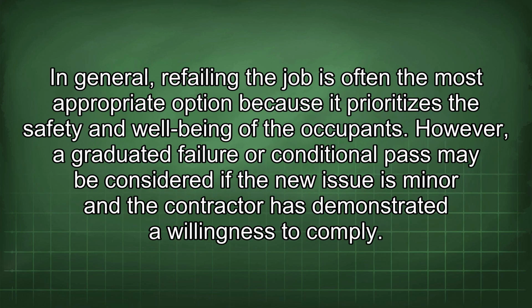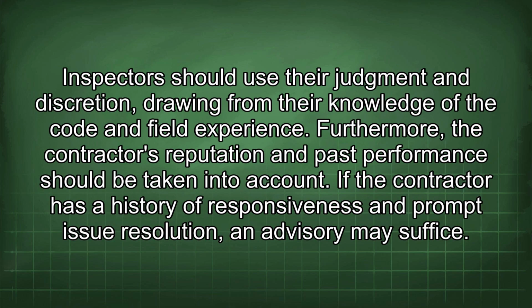In general, refailing the job is often the most appropriate option because it prioritizes the safety and well-being of the occupants. However, a graduated failure or conditional pass may be considered if the new issue is minor and the contractor has demonstrated a willingness to comply. Inspectors should use their judgment and discretion, drawing from their knowledge of the code and field experience. Furthermore, the contractor's reputation and past performance should be taken into account. If the contractor has a history of responsiveness and prompt issue resolution, an advisory may suffice.